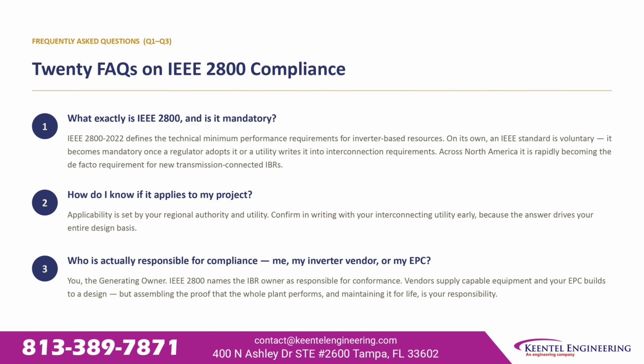What exactly is IEEE 2800, and is it mandatory? IEEE 2800-2022 defines the technical minimum performance requirements for inverter-based resources. On its own, an IEEE standard is voluntary. It becomes mandatory once a regulator adopts it or a utility writes it into interconnection requirements. Across North America, it's rapidly becoming the de facto requirement for new transmission-connected inverter-based resources.